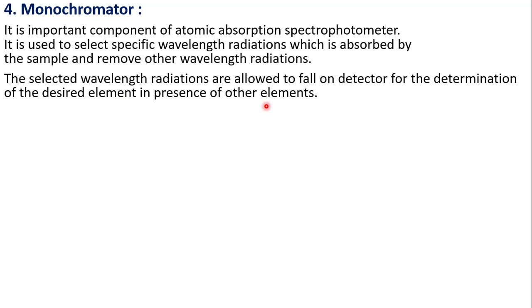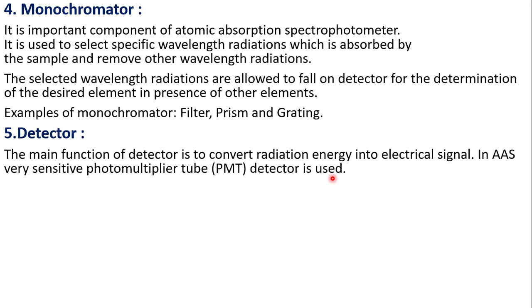Fifth one, detector. The main function of the detector is to convert radiation energy into electrical signal. In atomic absorption spectroscopy, a very sensitive photomultiplier tube detector is used. Sixth one, amplifier. It is placed between detector and readout system. The main function of the amplifier is to amplify the current signal given by the detector and send it to the readout devices.